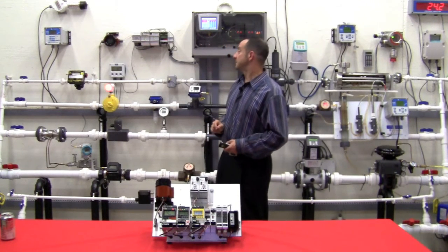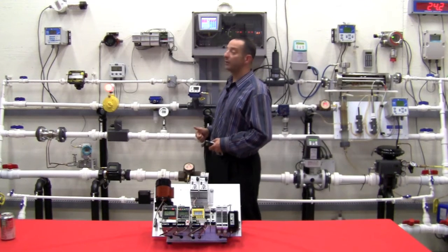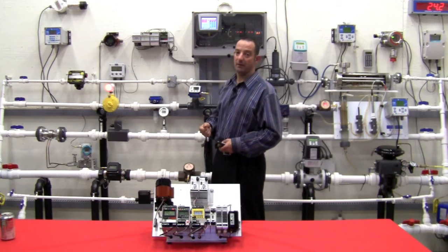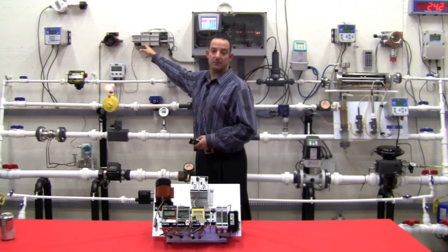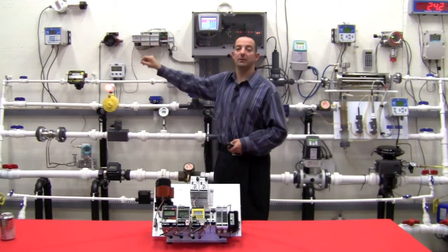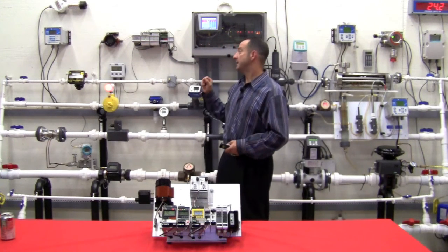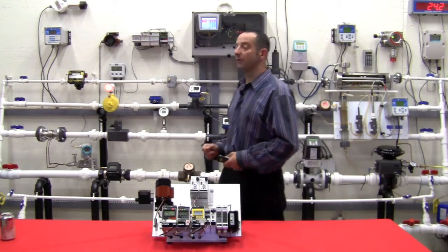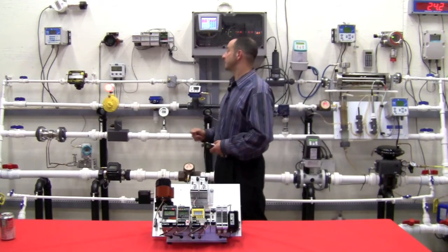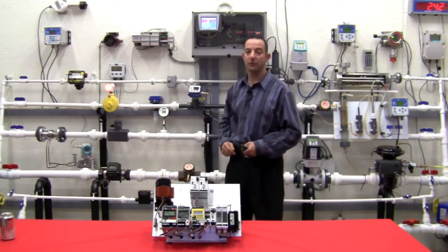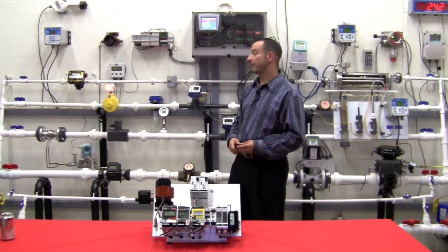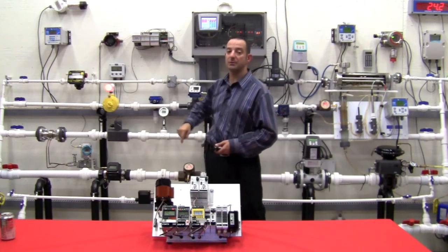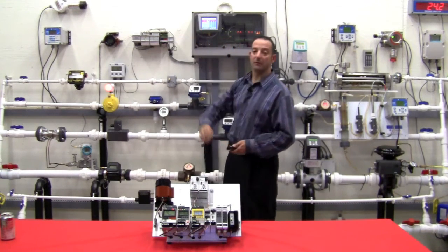All of our signals are isolated: input from output, and input to ground and output to ground on a channel by channel basis. So you have complete isolation on the I/O, and it's extremely high accuracy. All of our input modules employ 20-bit A to D converters, so you won't lose any accuracy bringing anything into a control system, and often you'll improve your accuracy because of the high accuracy front end on the module and then the digital communication over to the host.